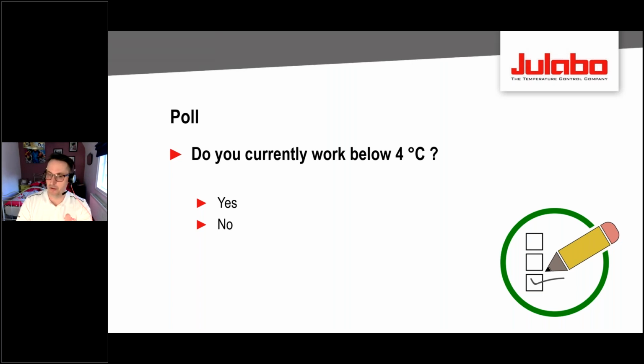If you want to work below 0 degrees C, straight away your chiller is going to cost a lot more. What I try to say to everyone we're sizing a chiller for is, if you're using tap water, you don't need to go below 4 degrees C. That means you don't need an expensive chiller, you can have an inexpensive one.